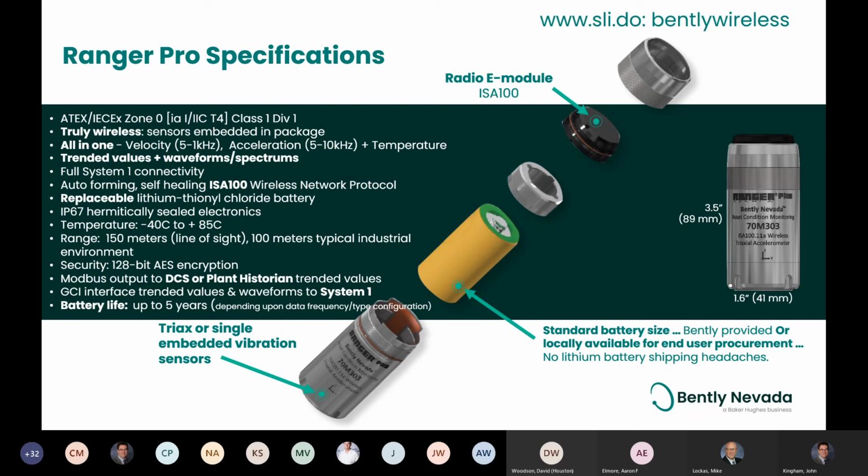Just be aware that the epoxy sometimes does not transmit temperature as well as the metal-to-metal temperature. And you can also use a magnet. Typically, though, the magnets are really going to do a poor job of transferring the thermal energy, so you might not get accurate temperatures, and if you don't have it positioned right, you may lose some of the high frequency content as well. But you would have that same loss in a walk-around program as well.